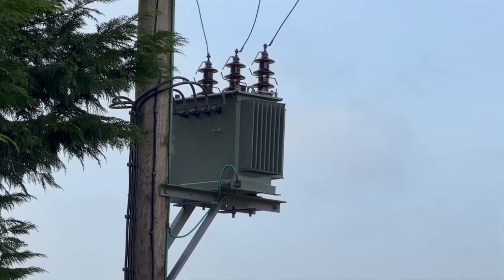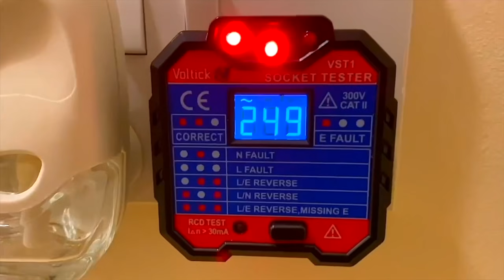The result? More nuisance tripping and more unnecessary callbacks for installers. myenergi says its answer is ZapSafe, a dual sensing PEN fault protection system built into every zappi charger. Instead of relying solely on voltage to detect an open PEN fault, ZapSafe also monitors what's happening on the protective earth, giving the charger a clearer picture of whether there's a real fault or just normal grid fluctuations. The company claims this reduces unnecessary disconnections while remaining compliant with BS 7671.